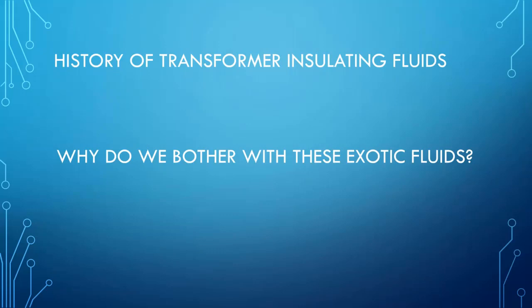I've had people ask me, why do we fool with these exotic fluids? Why can't we just use mineral oil? Well, here's the reason. In the 30s and 40s, mineral oil was used all over, indoors and outdoors. And our fire protection systems weren't what they are today. When a transformer failed and the upstream circuit breaker would fail to open, which happened on occasion, you not only got a transformer that's on fire, but most of the time the tank ruptured, and now you have a river of oil running down the hallway in a hospital that's on fire. So it's not an ideal situation.